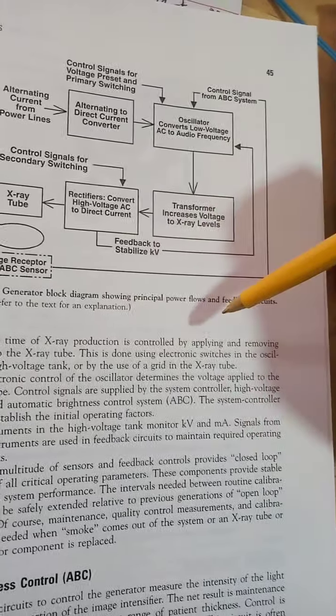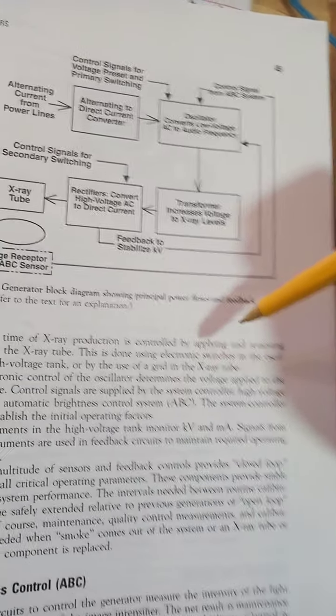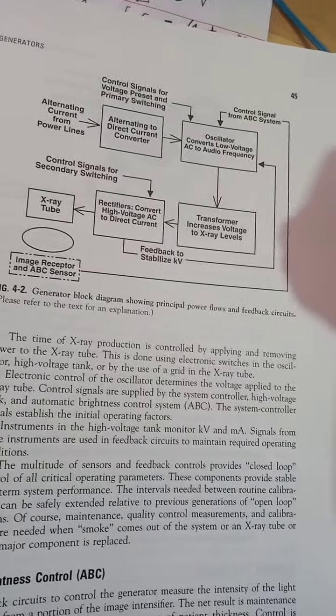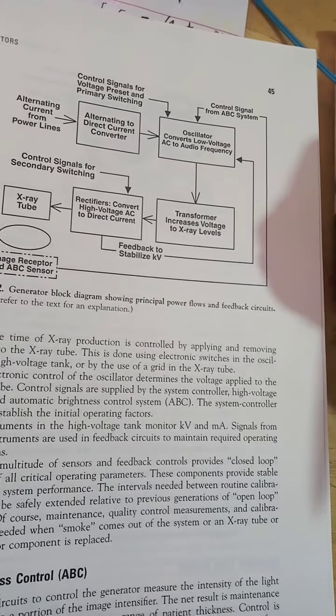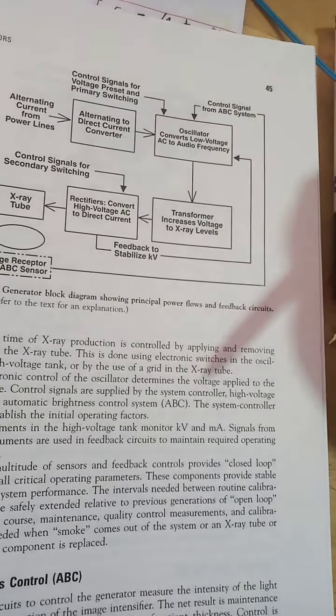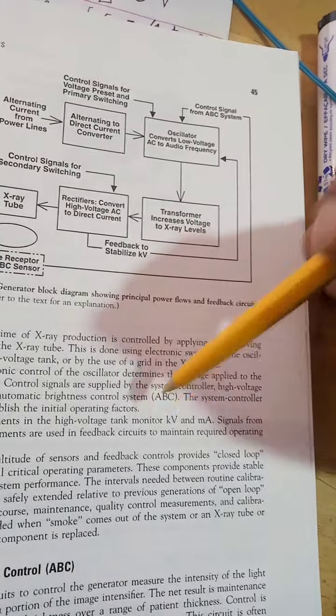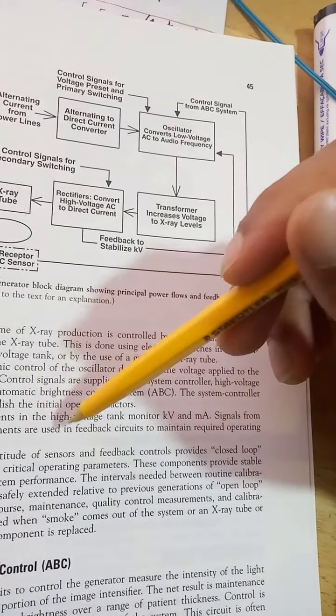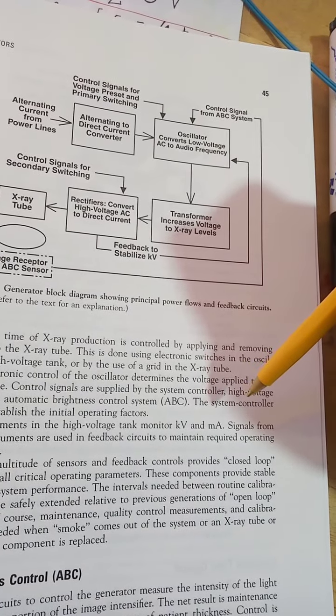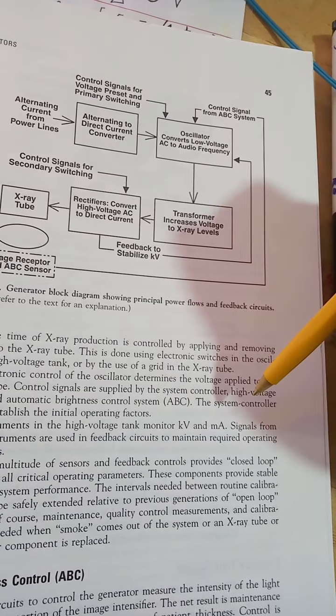This is done using electronic switches in the oscillator, high voltage tank, or by use of the grid in the X-ray tube. Electronic control of the oscillator determines the voltage applied to the X-ray tube. Control signals are supplied by the system controller, high voltage tank, and automatic brightness control system. The system controller signals establish the initial operating factors. The instruments in the HVT monitor the voltage and the current.